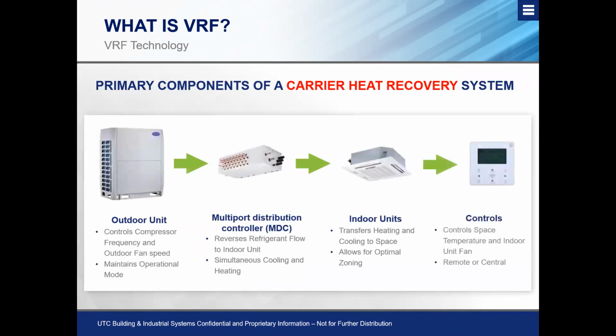Now this is where we start to change things up. So with the Carrier system that's referred to as the two-pipe heat recovery system, we have our outdoor unit, our indoor unit, some form of control, just like we did on the heat pump system. But now what changes is what we call our MDC. Some people call these flow selectors, some people call these branch boxes. They're essentially doing the same thing, but they have different acronyms and names or identifiers depending on which manufacturer you're dealing with.